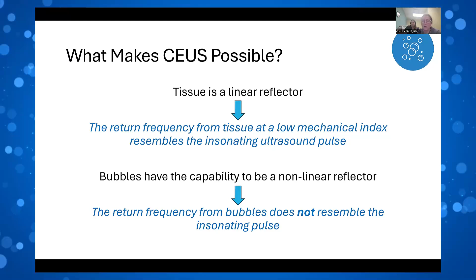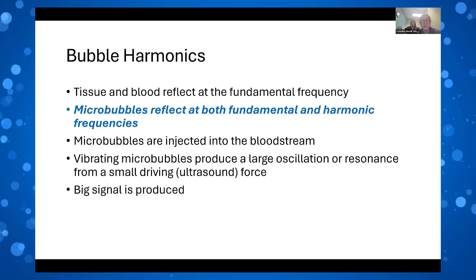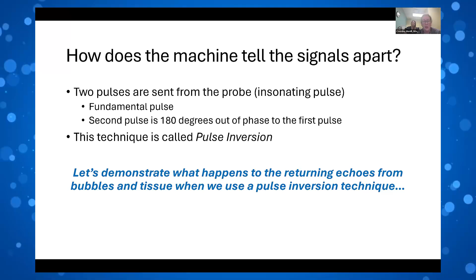Tissue and blood reflect at the fundamental frequency, whereas microbubbles reflect at both the fundamental and harmonic frequencies. Microbubbles are injected into the bloodstream, and those vibrating microbubbles produce a large oscillation or resonance from a small driving ultrasound force. So ultimately, a big signal is produced. How does the machine tell the signals apart from the tissue and the bubble? Well, we're going to start with the insonating pulse. Two pulses are sent from the probe. We have a fundamental pulse, and then a second pulse sent from the probe, which is 180 degrees out of phase to the first pulse. This technique is called pulse inversion, and it's critical to contrast enhanced ultrasound. Let's demonstrate what happens to the returning echoes from bubbles and tissue when we use a pulse inversion technique.